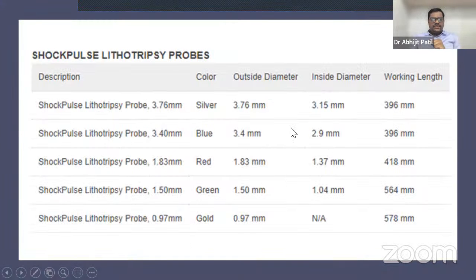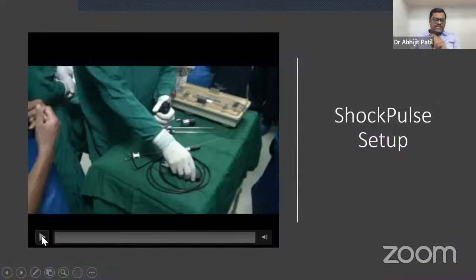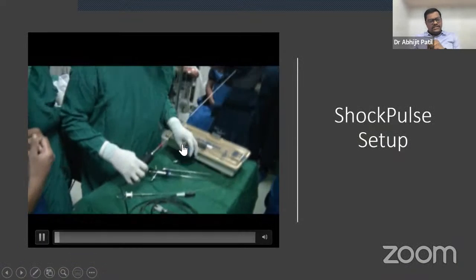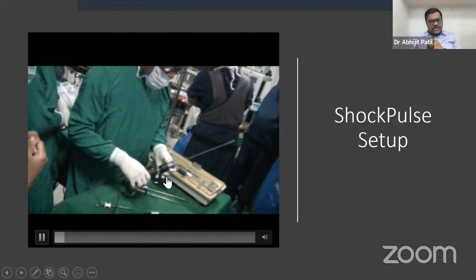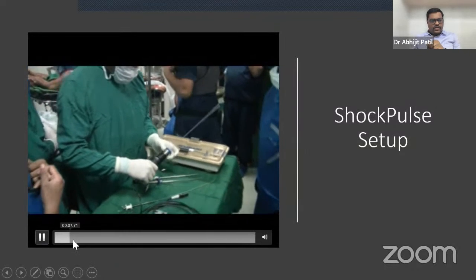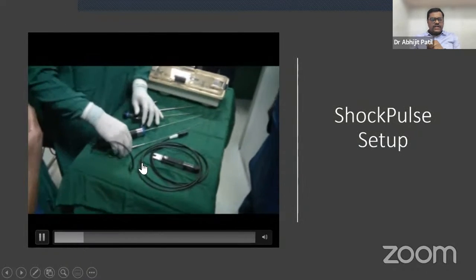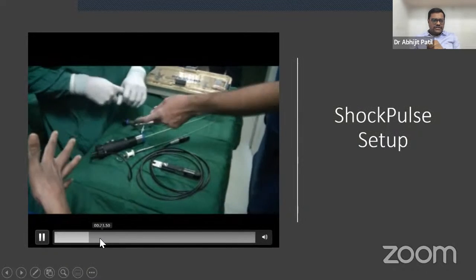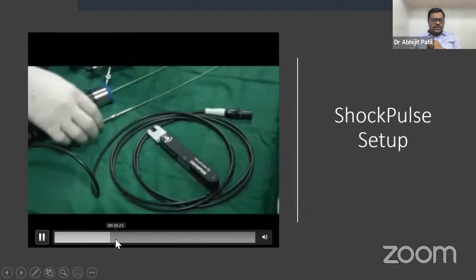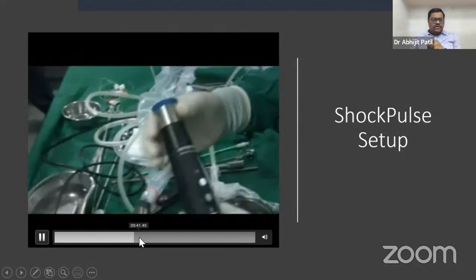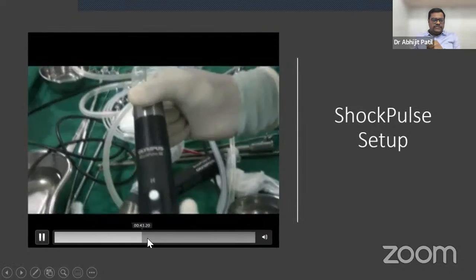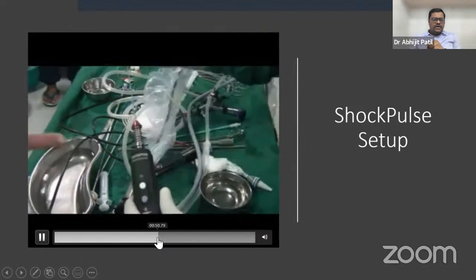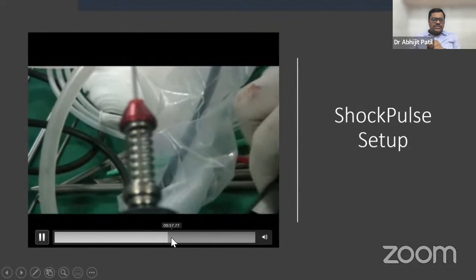These are the various probes which are available. As I showed earlier also, it is 1.9 mm for Trilogy and 1.8 mm for Olympus Shock Pulse. Now the setup for Shock Pulse, as you are seeing in the animation, this is a real-time video where this is the transducer, this is the probe, this is the cable, and this is the wrench. Now, how do you remove that? You unscrew it, then take a torque wrench and unscrew using the torque wrench.